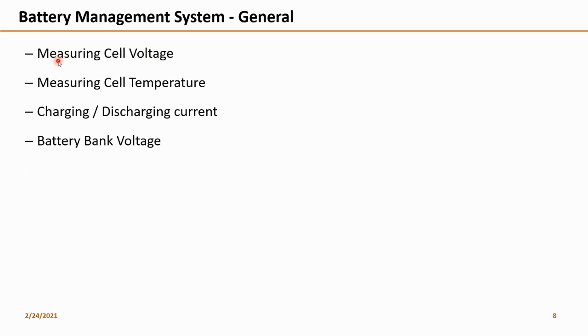Nowadays they have a UPS system, not with a single battery, but maybe a bank of batteries tied to it. Measuring cell voltage is not a big engineering task. Even still nowadays, in power plants or any plant running on shifts, every shift people go and measure the cell voltage of each individual cell, maybe at every shift or every day.